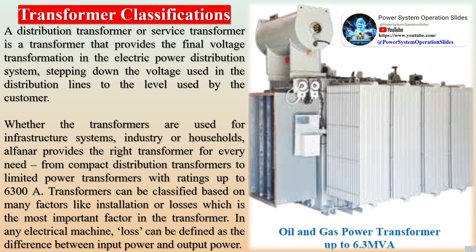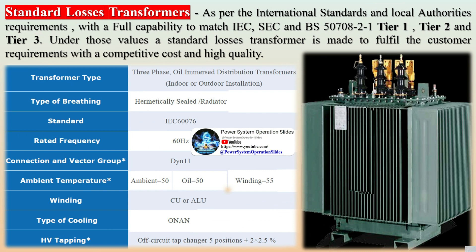Vector Group: The Vector Group is the International Electrotechnical Commission (IEC) method of categorizing the high-voltage (HV) and low-voltage (LV) winding configurations of three-phase transformers. The Vector Group designation indicates the winding configurations and the phase angle difference between them. The possible connections are: D – delta connection, Y – star connection, Z – zig-zag connection, N – neutral exists for connection outside the transformer. Each unit in the Vector Group refers to 30 degrees of displacement. For example, a Vector Group Dyn11 is delta on primary, star on secondary, with neutral brought out and 330-degree phase displacement.